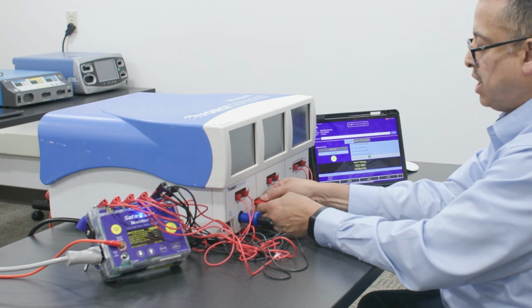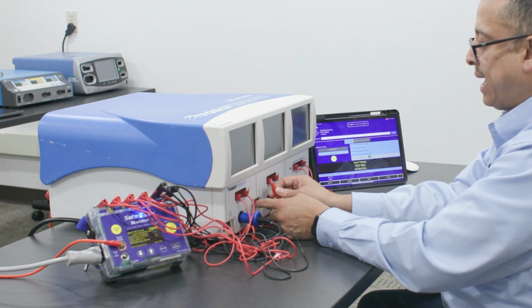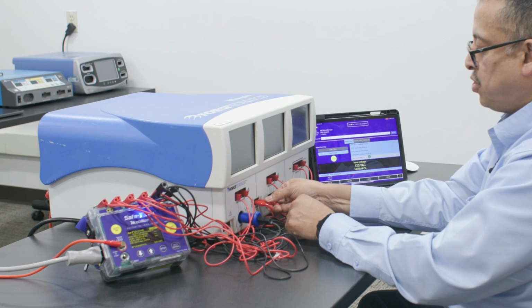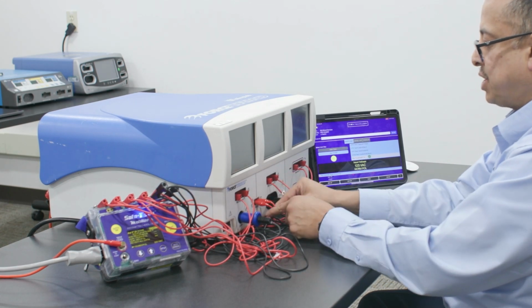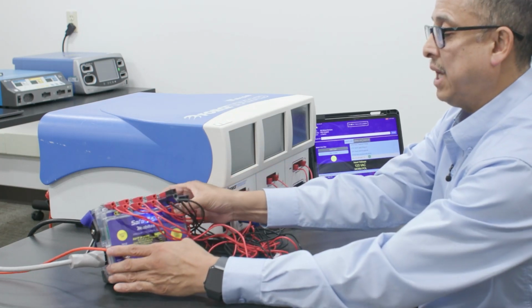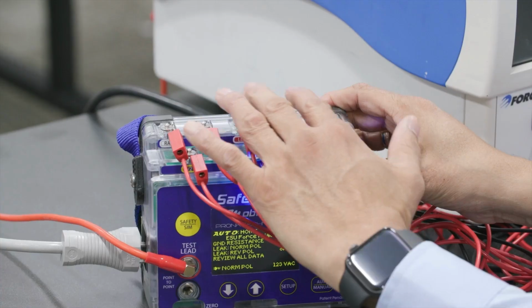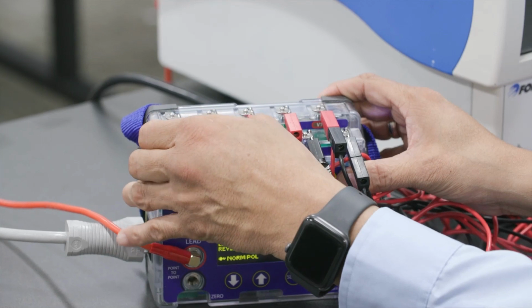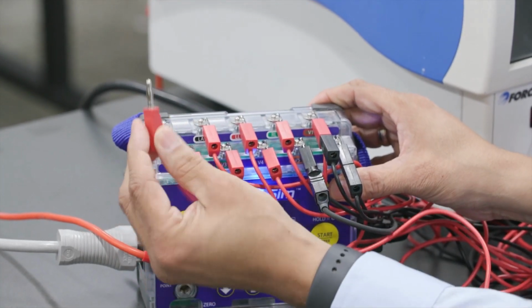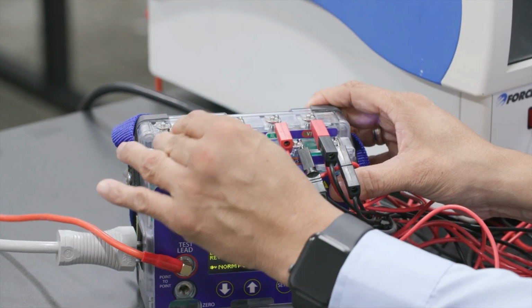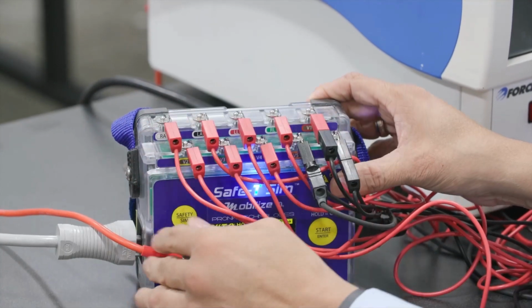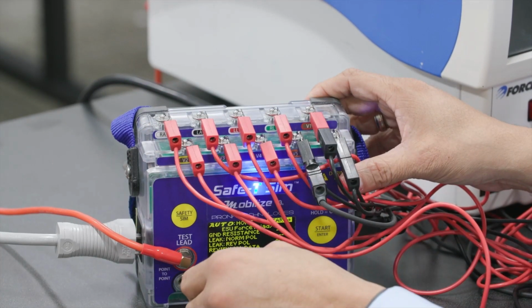We also want to connect our REM connections to the safety analyzer using these alligator clips. To connect them to the safety analyzer, you want to connect them to the upper section, the ECG snap section, and you're going to take the banana plugs of each one and just slide it under each one of the snaps here. Doesn't matter what snap you're connecting it to. There's no particular order you need to do it in.